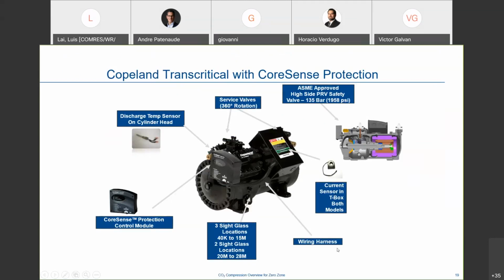Well, the compressor comes with a number of features already on it. It comes with CoreSense, but one of the differences between the Discus model CoreSense and the 4MTL model CoreSense is that it already comes standard with the discharge temperature sensor installed and wired into the CoreSense, which the Discus don't. So that's part of the feature there. The valves, you can turn those discharge valves and suction valves 360 degrees, so you've got flexibility there. So that's important. Another thing is that this compressor has an oil flinger, similar to the air-cooled models. If you know our Copelametic air-cooled models, they have an oil flinger, most of them. And so this one does as well.